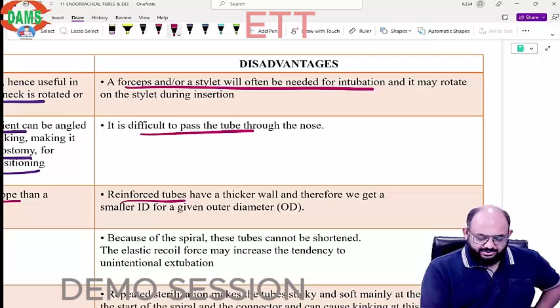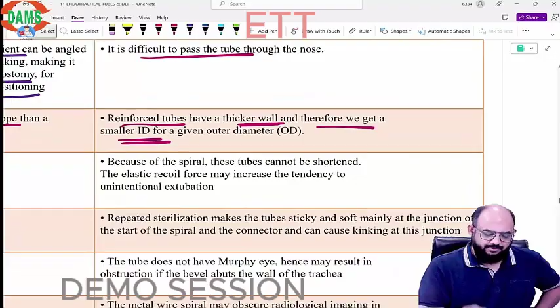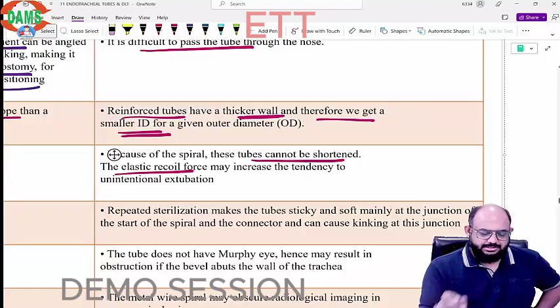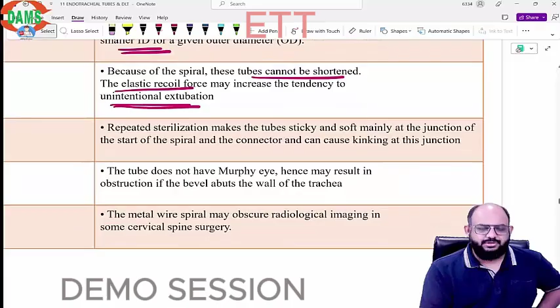Difficult to pass the tube through the nose. Reinforced tubes have greater wall thickness. Therefore, we get a smaller internal diameter for a given outer diameter. Because of the spiral, these tubes cannot be shortened, and elastic recoil force may increase the tendency of unintentional extubation. Repeated sterilization makes the tube sticky and soft, mainly at the junction of the start of the spiral and the connector, and at that point the tube can become kinked.